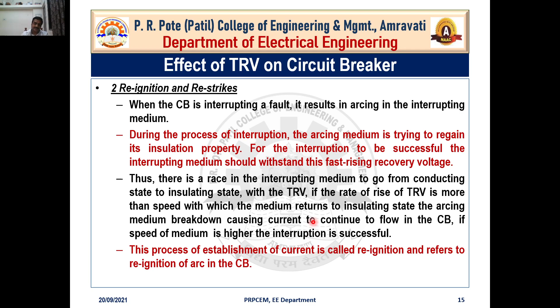If the rate of rise of TRV is more than the speed with which the medium returns to the insulating state, that is the dielectric strength of the medium, then the arcing medium breaks down, causing current to continue to flow in the circuit breaker. It means that if the rate of rise of TRV is greater than how fast your medium regains its insulating properties, then the current will continue to flow inside the circuit breaker. The vice versa situation is that if the speed of the insulating medium is higher, then you can successfully interrupt the fault current. This process of re-establishment of current we also call reignition, and it refers to reignition of the arc inside the circuit breaker.